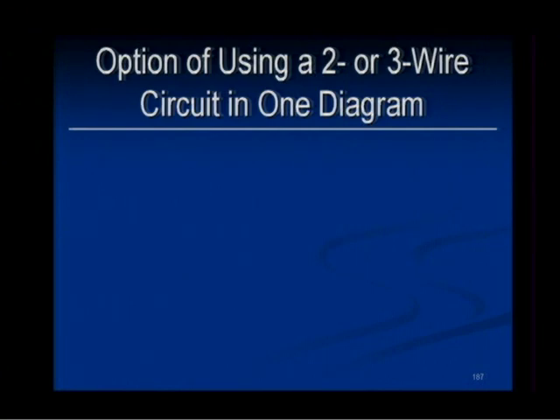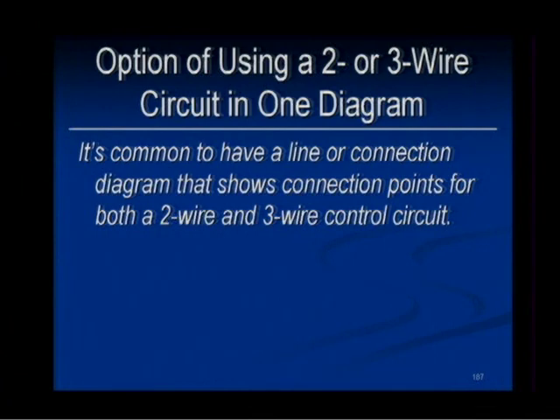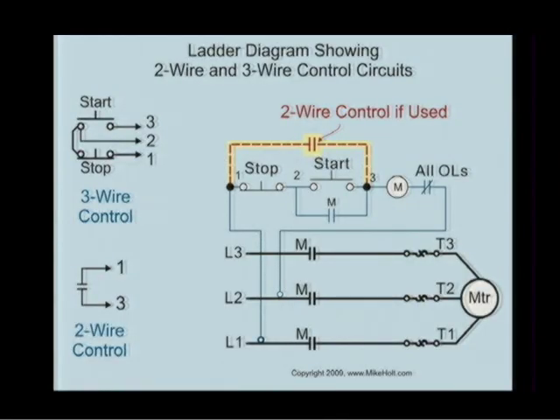Option of using 2 or 3 wire circuits in one diagram. It's common to have a line or a connection diagram that shows connection points for both 2-wire and 3-wire circuits. No, not another 3-wire circuit. Okay, so here's my connection diagram. And it's showing a dotted line that here's the option. If you want to, you can use a start-stop between points 1 and 3. Or don't use a start-stop. Optionally, put a 2-wire control circuit. That's what we're trying to do.